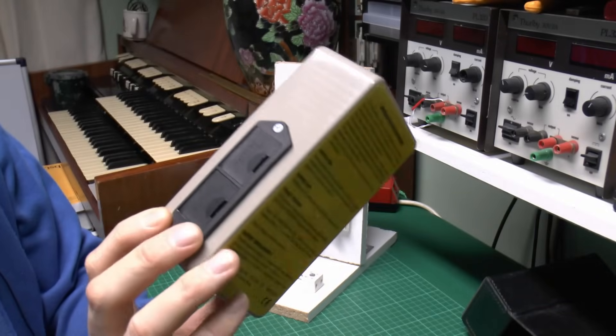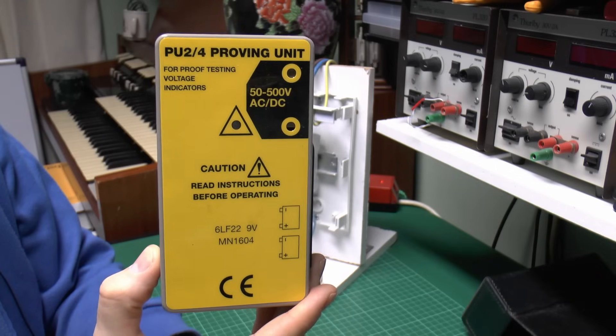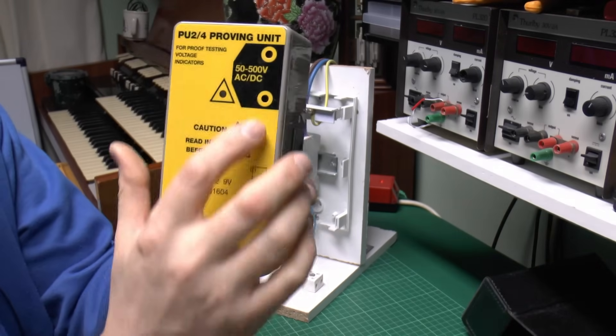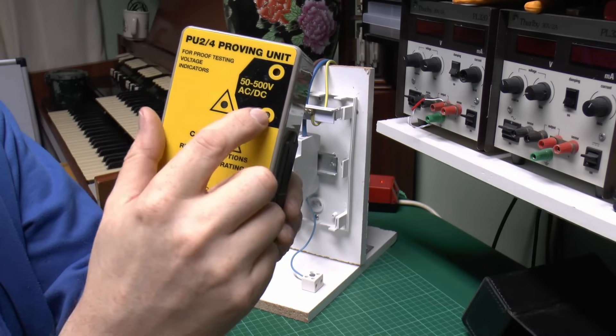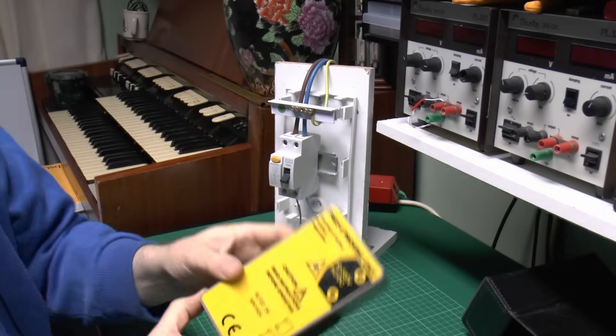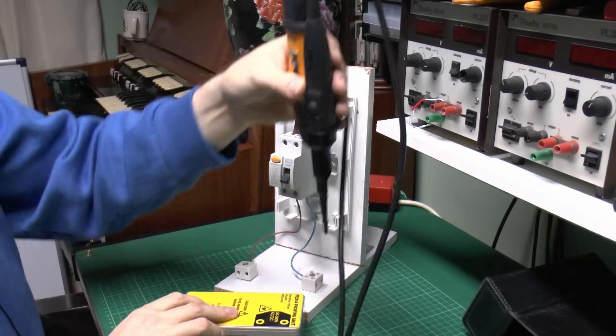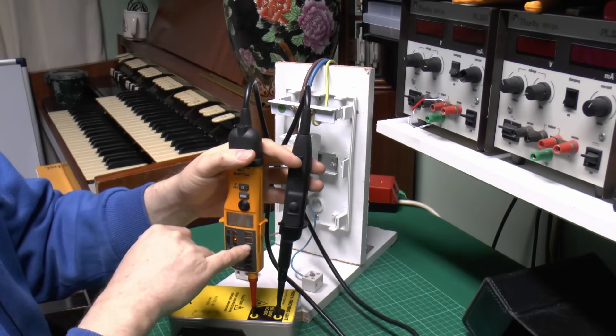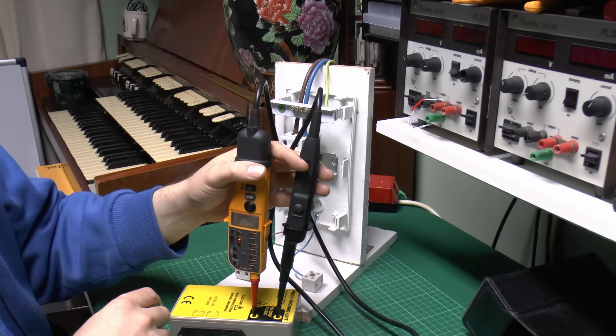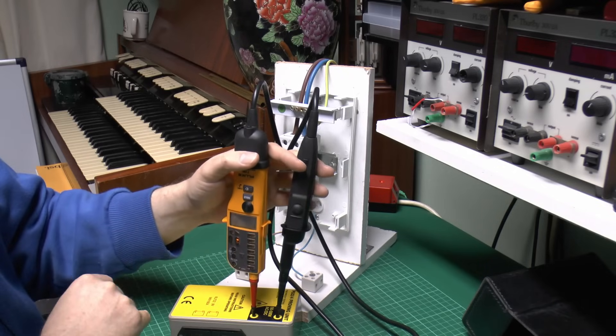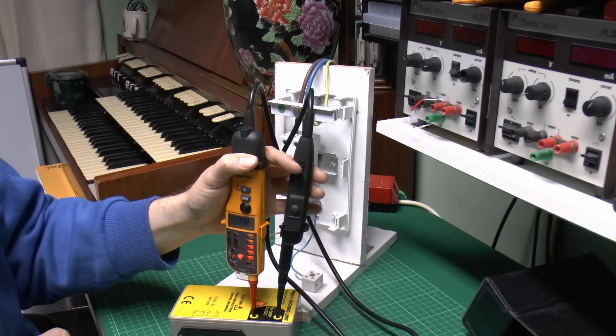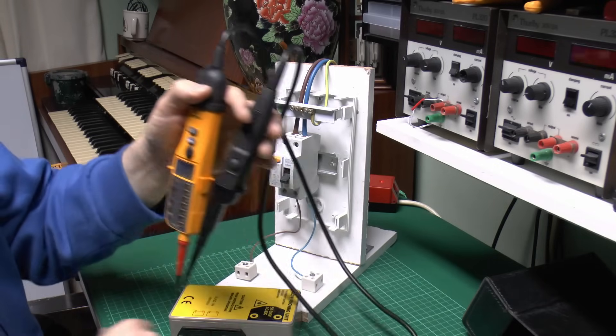And in those circumstances there is a solution of course, and it's one of these or something like it. Now as it says in the box here, this is a proving unit, and essentially it's just battery powered with the batteries in the side, and as it says on the front there it just creates the voltage up to around 500 volts, so you can then confirm that the test instrument you're using is still working. And they're very simple to use, simply got the two holes here, one for each of the test probes, and there's actually a switch inside so it only turns on when you actually press down into the holes, so of course that's a bit of a safety feature there. And simply just to confirm that the test equipment is working, simply get the device here, placing the two probes into the holes and then just pressing down, and of course it should illuminate here.